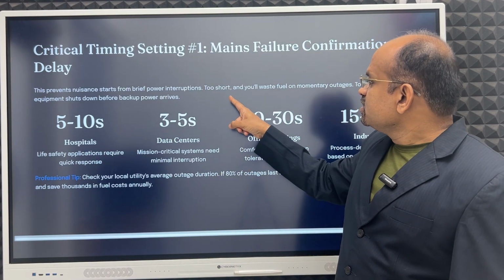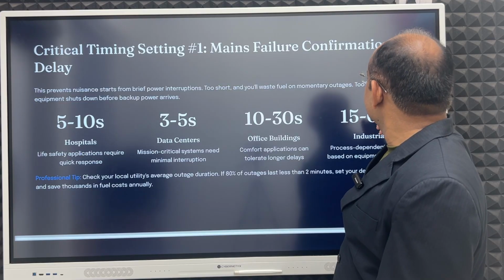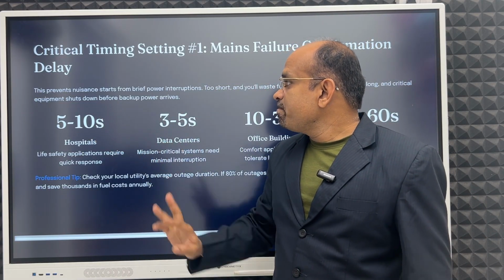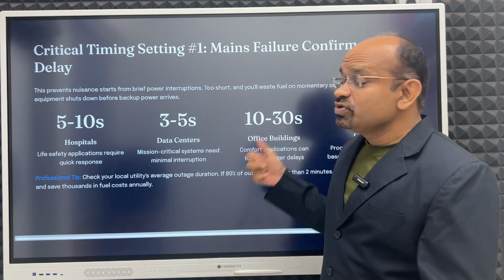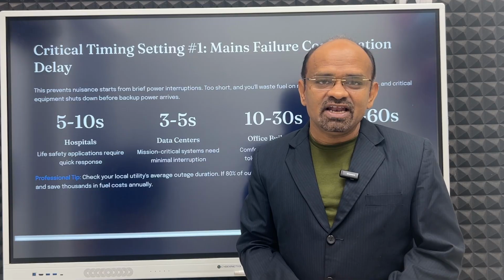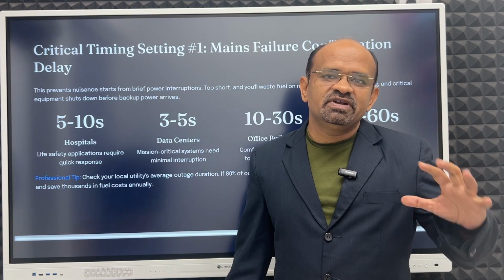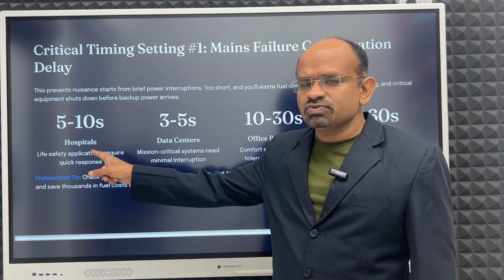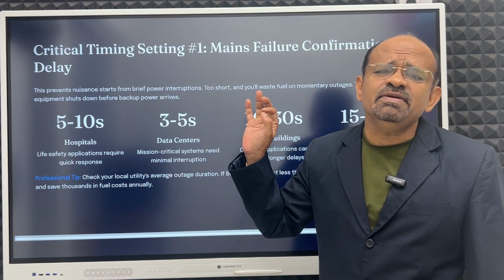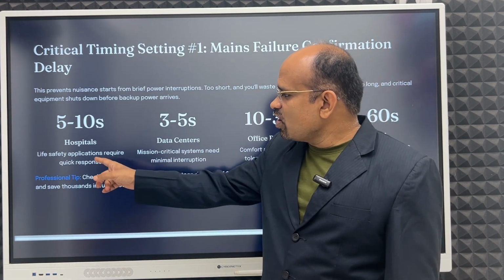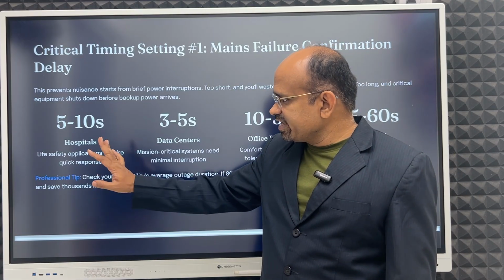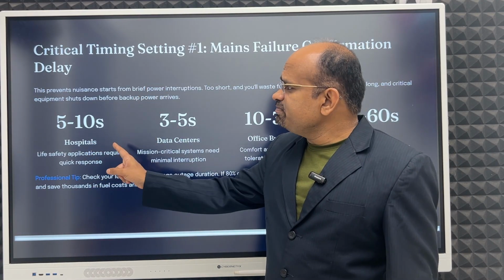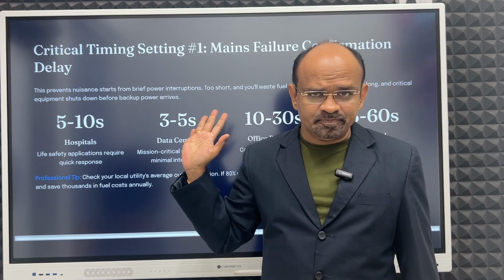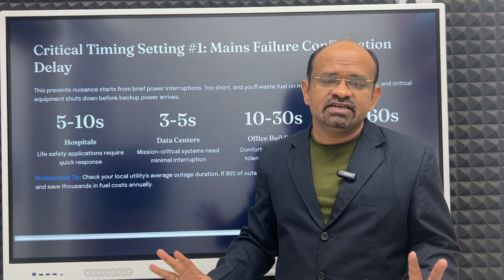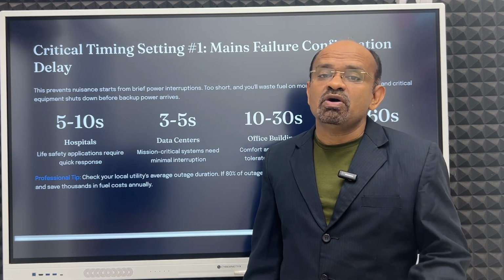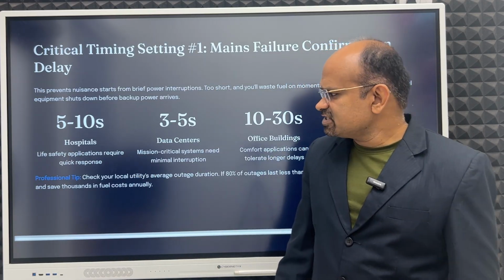Okay, brief power, I told you. Too short and you will waste fuel on momentary outages. Too long and critical equipment shuts down before backup power arrives. So too long also is not advisable, because then backup units should survive up till that time. So we will see the examples for hospitals, which is very critical, like operation theaters and all. Life saving devices, life critical devices in hospital. So life safety applications require quick responses, 5 to 10 seconds. So within 5 to 10 seconds, this should confirm the delay. You should keep 5 to 10 seconds to confirm that there is a problem in the input power. Then start the further switching process.